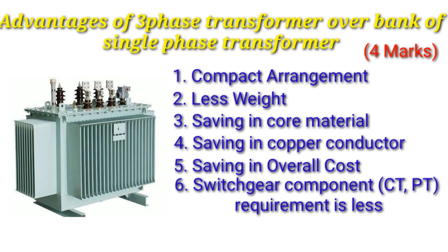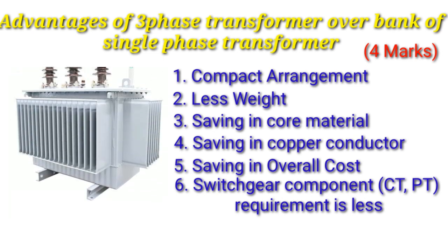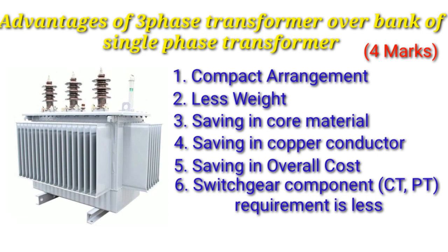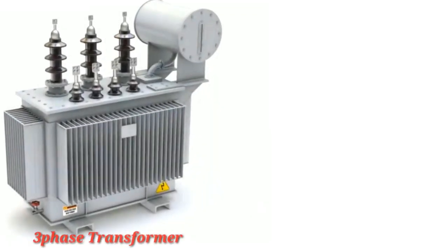Next point: switchgear components such as CT and PT required are less. In a bank of single-phase transformers, we use CT and PT for three transformers, but in a single unit three-phase transformer, only one CT and PT is used. Next point: higher efficiency. These are all the advantages of a single unit three-phase transformer.